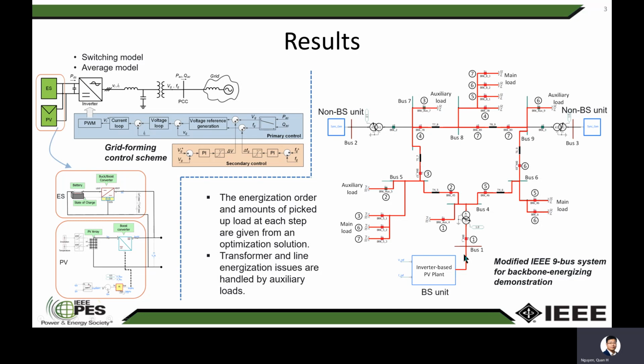And this unit is used to energize transformer and transmission lines and also pick up loads. The energizing sequence and how much power, how much load are being picked up at each step are given from an optimization solution. And the steps are shown in the circles here. During this process, we found out that if we energize a transmission line and or unload the transformer, there will be inrush current. And we solved this issue by adding auxiliary load at the secondary side of the transformer and transmission lines.